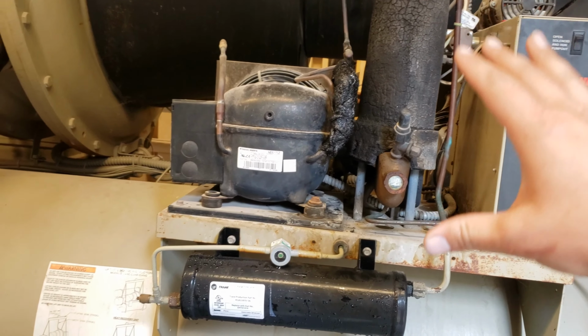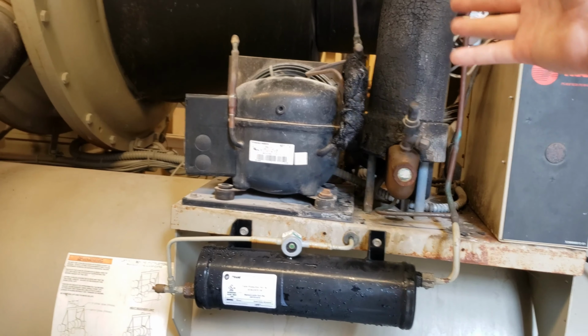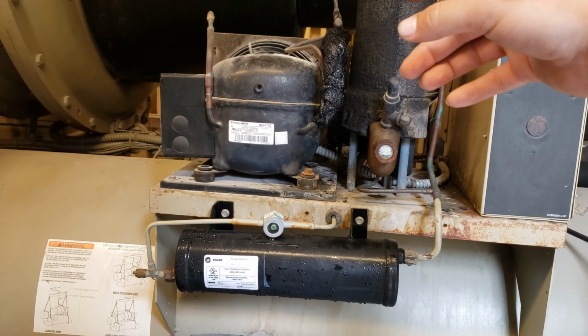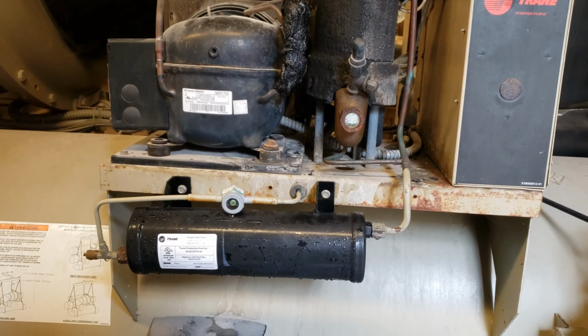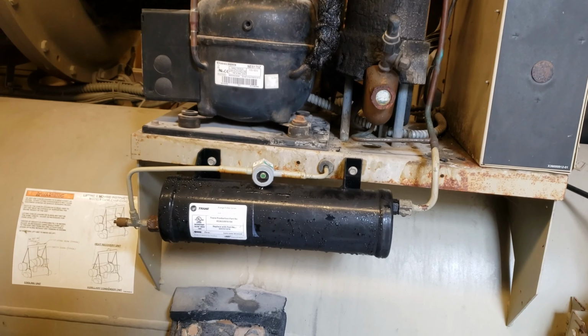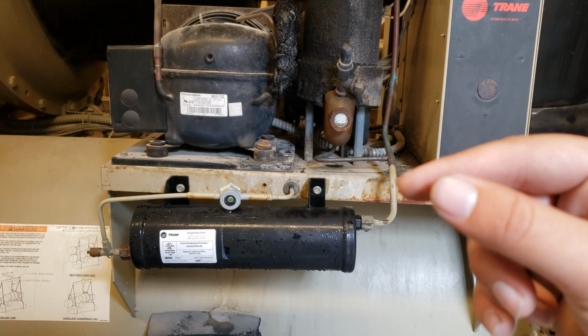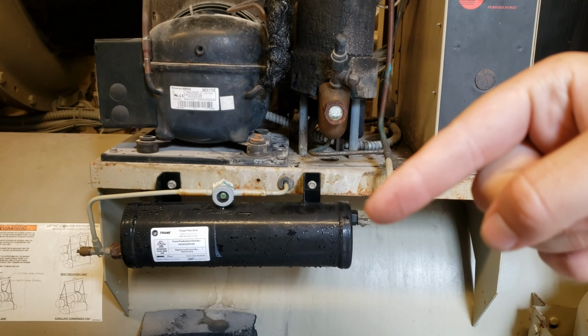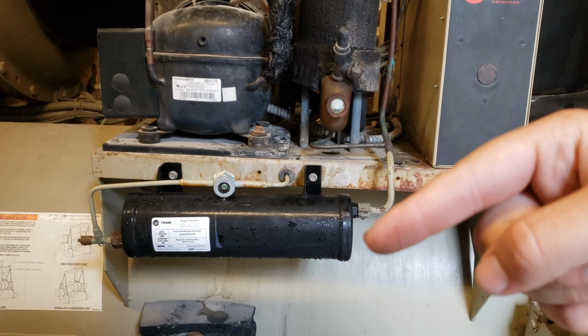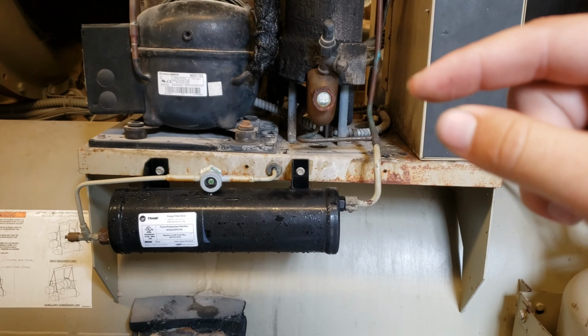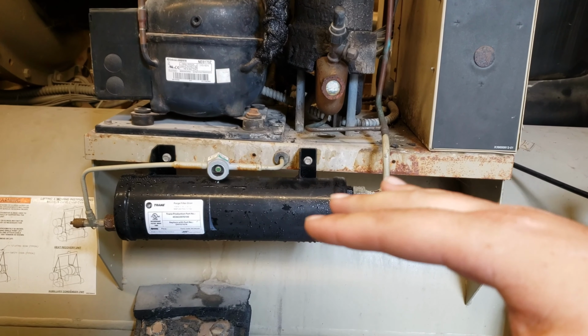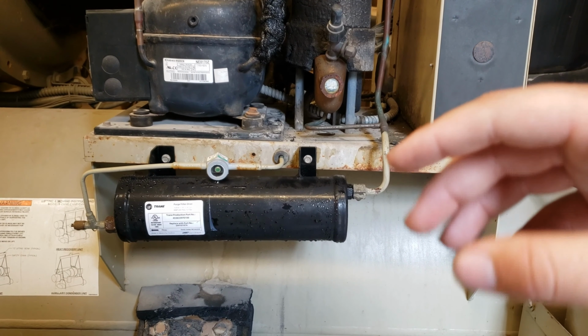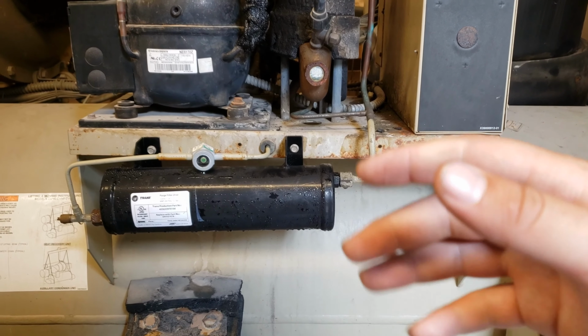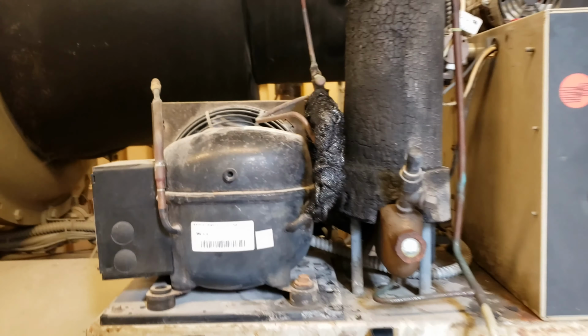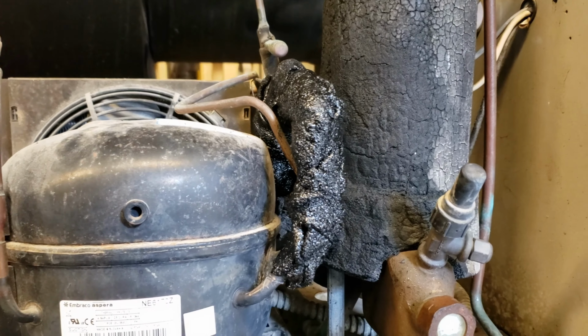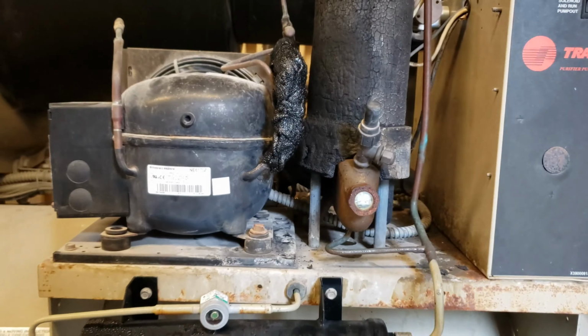Anyway, I tore all that apart, ripped all the old insulation off, and then I wasn't able to get those threads cleaned up in there to where I could thread the sensor in like it's supposed to be. So what I did was, where that tip is, I put a zip tie on that tip, which made that sensor sit at an angle intentionally, so that the tip where the sensor is actually made surface contact with the pipe. And then I just put a secondary zip tie further up, not tight, just enough to help hold it steady, and then re-insulated it really well with some cork tape. Probably overdid it more than I needed to, but I wanted this thing to really work well.